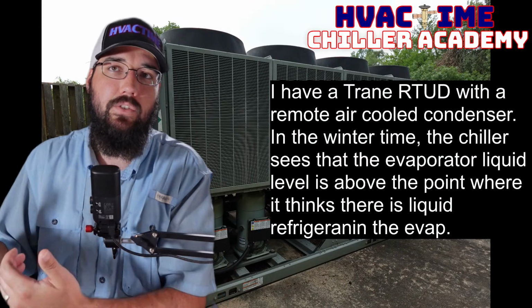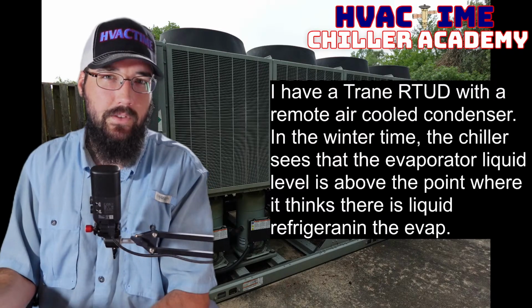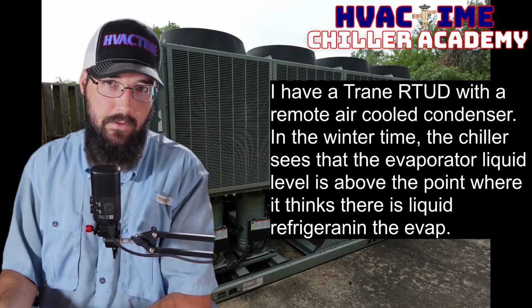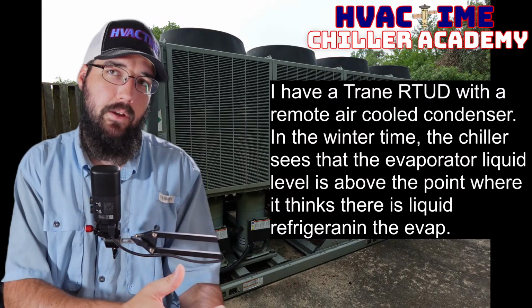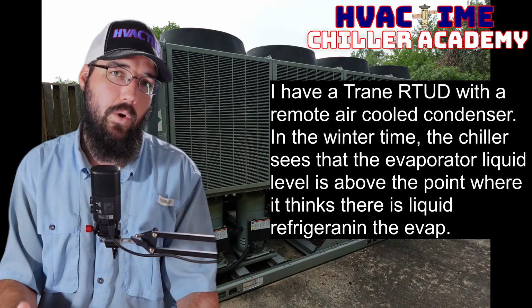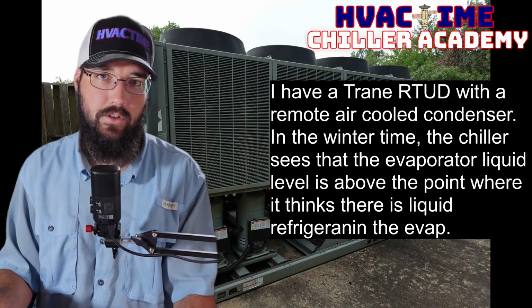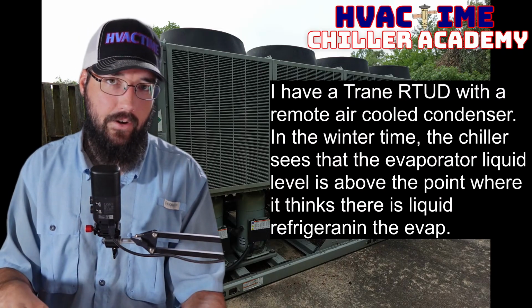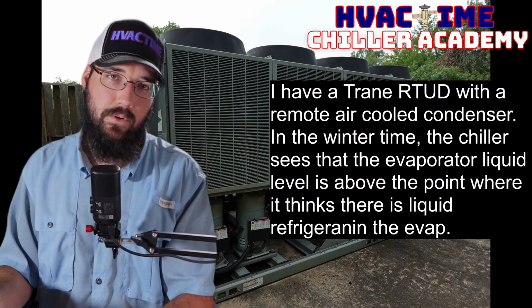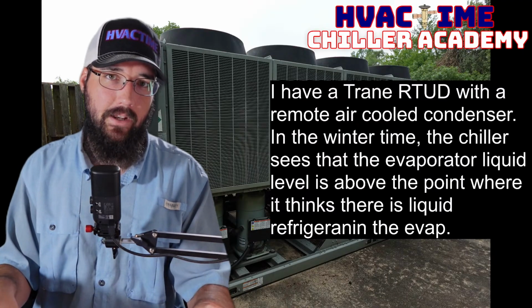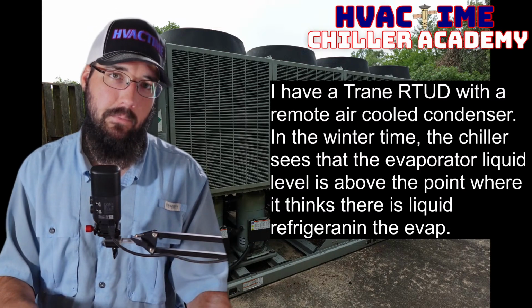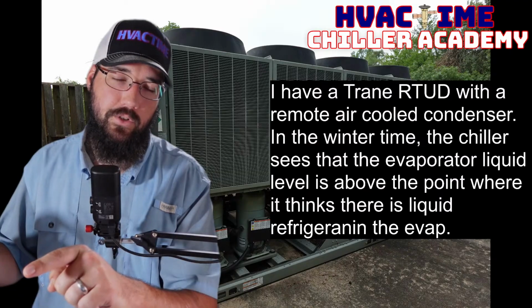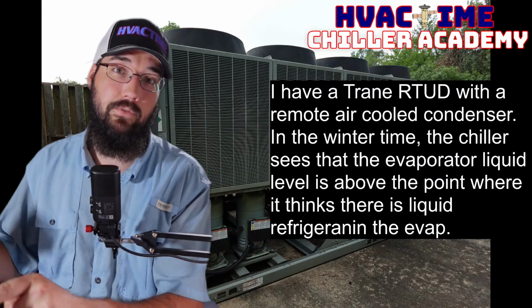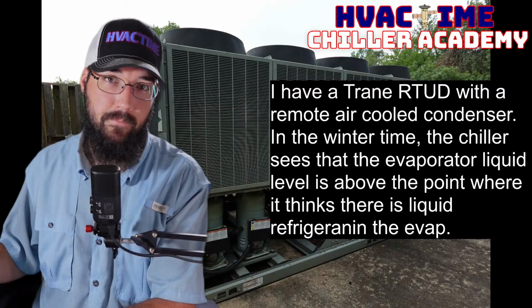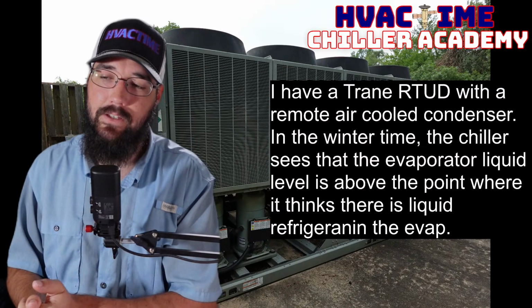So again, I don't think it's coincidence that this is a low ambient problem. But I think that would be a reasonable explanation as to how to explain the condition, why the liquid levels are showing higher when it is having a problem. That would make sense to me as to what I might expect to see. But I think that is a symptom of the oil issue, which the oil issue may be a symptom of head pressure control problems. I'd be curious to your thoughts on that, or if anybody has any additional thoughts on that.